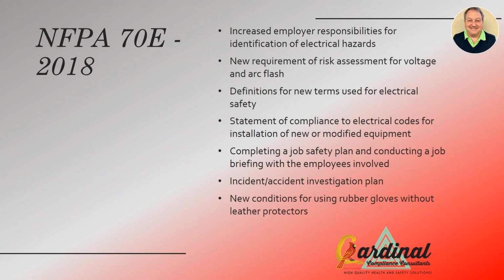They're raising the bar because of the increased level of injuries and accidents in electrical work. You're now responsible for identifying your hazards, and they want you to do a deep dive on the risk assessment of both voltage and arc flash. They want you to not only understand the voltages and levels of arc flash you're working with, but to have your people trained at these levels. Traditionally there are two levels of electricians: those qualified in 600 volt systems and under, and those working on high voltage. There are different skills, techniques, and equipment involved, so you have to decide whether you'll supply that equipment and to which level you'll train your people, including which level of arc flash. That's all up to you.